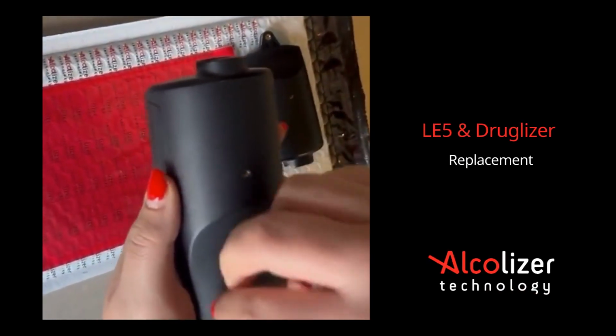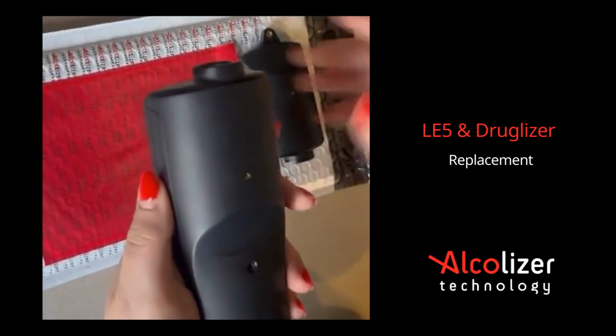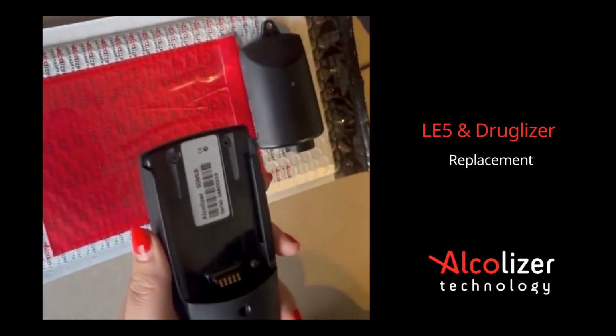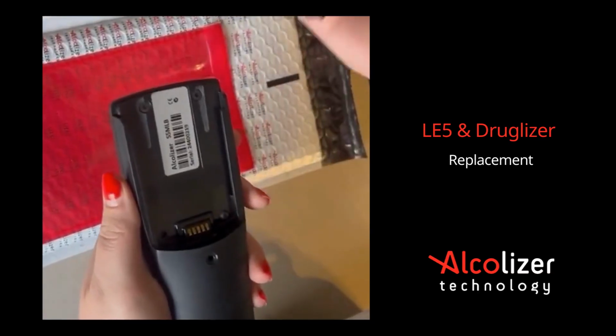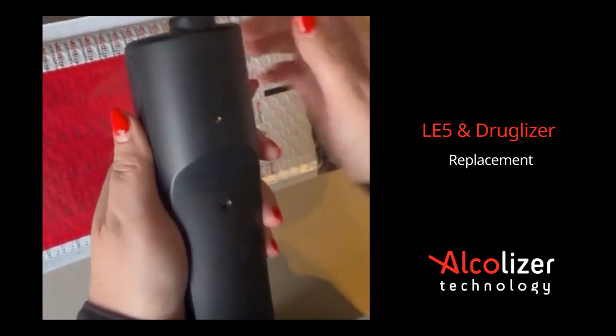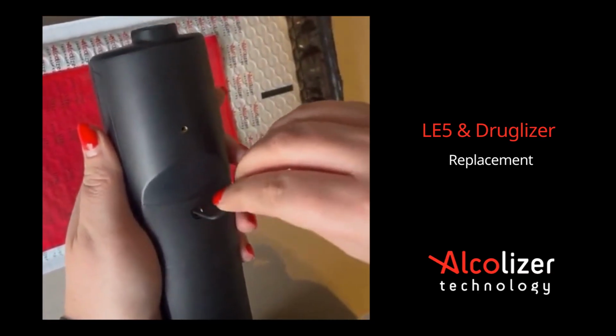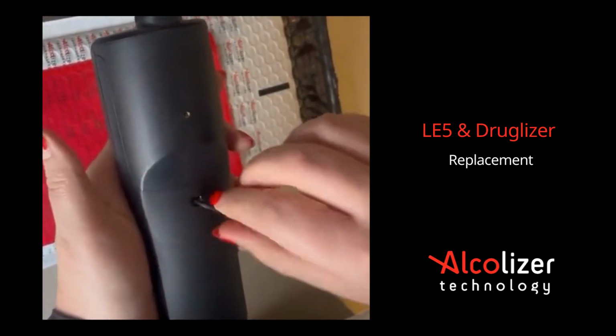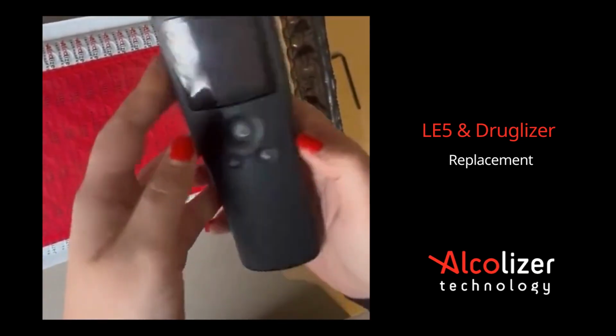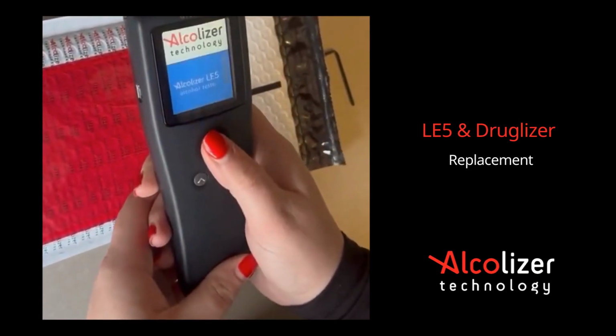To replace the module in a LE5 and Druglizer with the device turned off, use the Allen key provided to remove the screw. Swap the old module with the new calibrated module, reinsert and tighten the screw to secure it in place. Turn the device back on to resume operation.